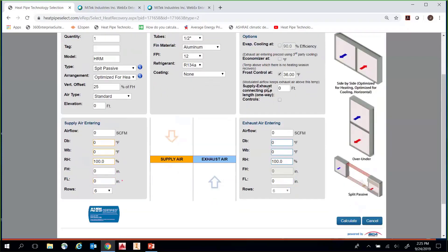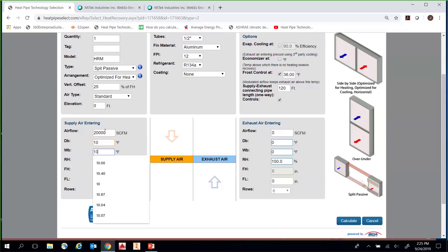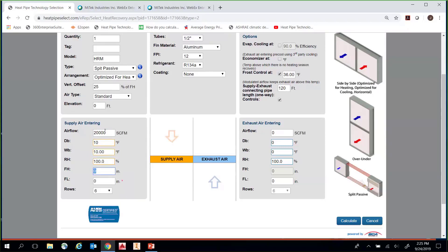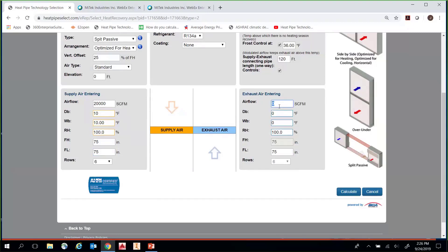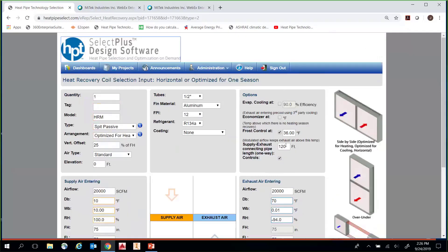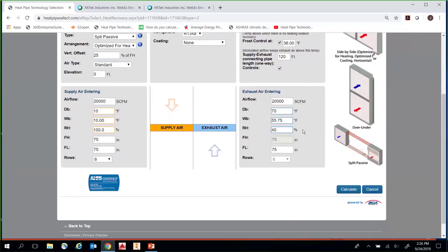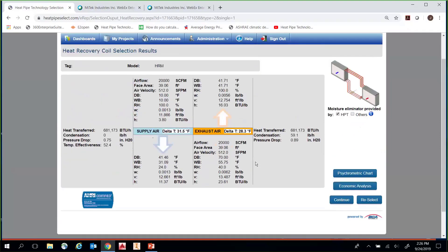Keeping coating as none. I'll set separation to 120 feet — that's the maximum we can do — and select controls for the modulating valves. For this example, it's a slightly larger system: 20,000 CFM with winter conditions of 10°F dry bulb and wet bulb. I'll max out fin height at 75 inches. Fin length at 75 inches. Six rows. Exhaust side: 70°F dry bulb, 40% RH. After calculating, the results are identical in structure to what we saw with the DSO.